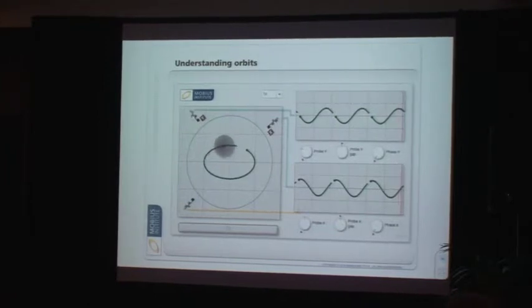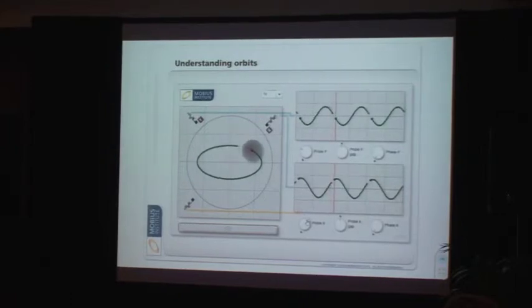So basically we have the two probes, and most of the software you use does all this compensation, so that when you look at the raw signals, that is what came from the probe. But if you look at compensated data and look at the orbit, you can orient yourself to say, well, okay, that is vertical and that is horizontal. But do check with your software whether that's really what you're looking at, horizontal, vertical, regardless of where those probes are mounted. But that all depends on the shape, what sort of movement you're getting.